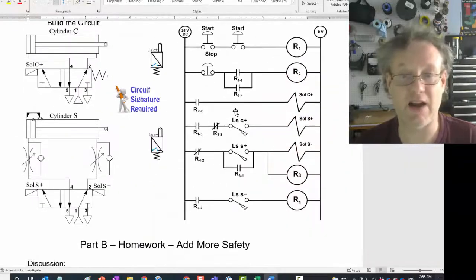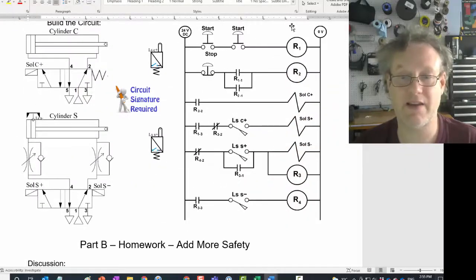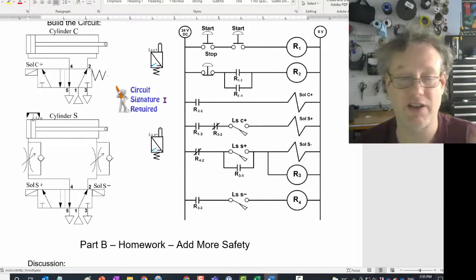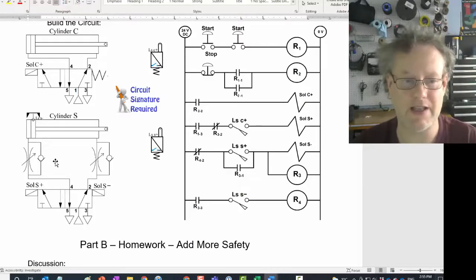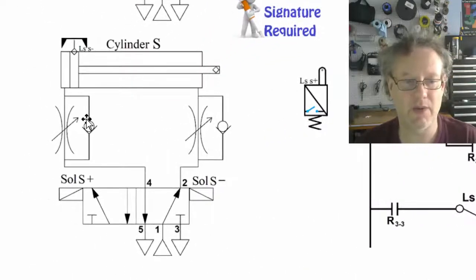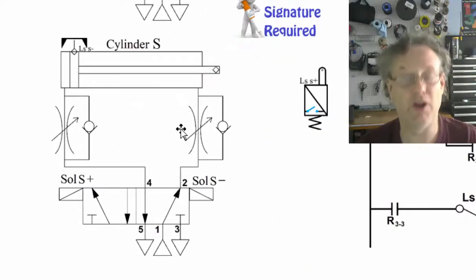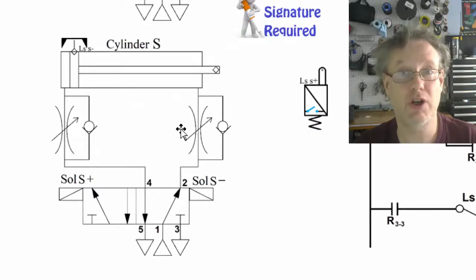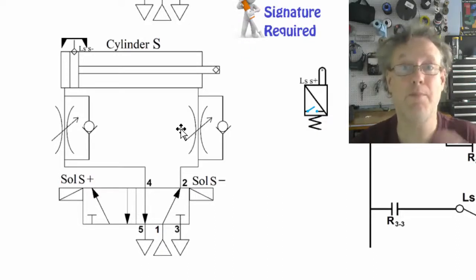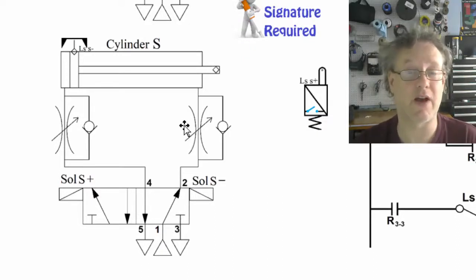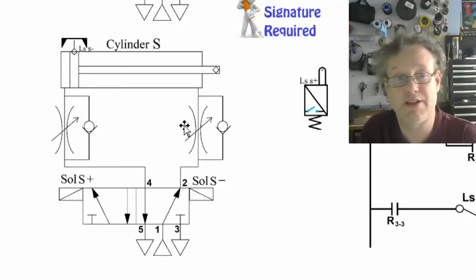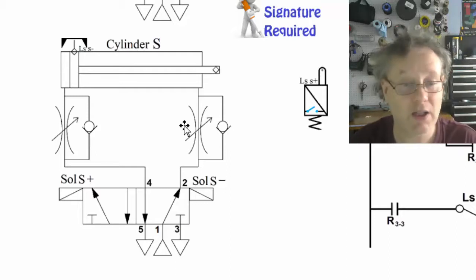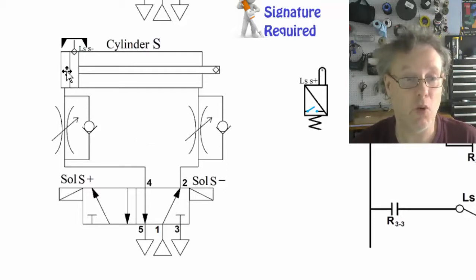So essentially here's the ladder logic. So hook this all up. And I think you guys just hook this up. But the one thing I have to stop and highlight is this. Let's just take a look at this. Okay, here we go. I've got some non-return throttle valves here, which are metering valves. I'm using them as metering valves. And as you know, we always meter out, right? So we're throttling the air coming out of a cylinder.